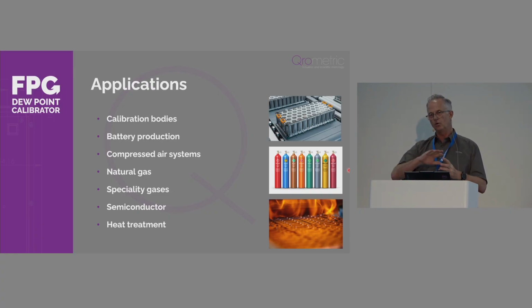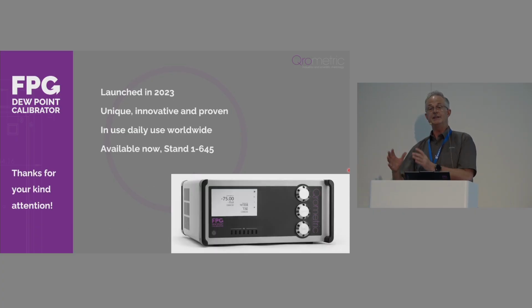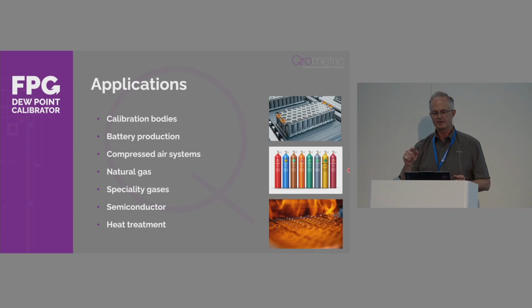So we've gone more directly to the calibration laboratories, who need methods for calibrating dew point sensors and moisture instruments. Battery production is a very, very typical end customer. Compressed air systems, natural gas, the ones I mentioned earlier. So we're finding very good uptake from industry customers, where they can do the calibration now on-site themselves with a relatively modest investment, with many, many benefits from a quality and a financial perspective.